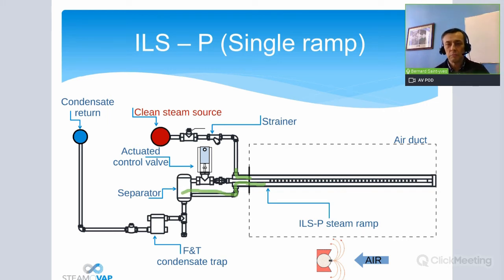The separator is a very simple device, but everything inside is made to, in fact, remove any moisture from the steam. So it's looking like a cylinder, and inside this cylinder there will be baffles and screens. And these baffles and screens will make the steam circuit very complicated. So then any moisture contained in the steam will catch on the baffle and the screen and fall out to the condensate trap here and can be returned back to the boiler. Okay, because it's still under pressure. All this is under pressure. And then the outlet of the separator will be clean steam, and clean I would say without moisture, steam going to the control valve and then directly to the distribution in the air duct.